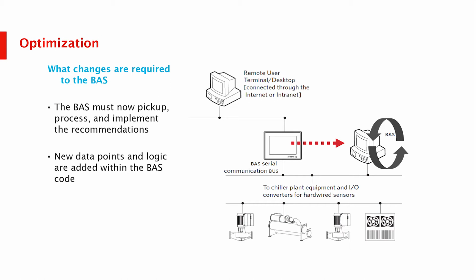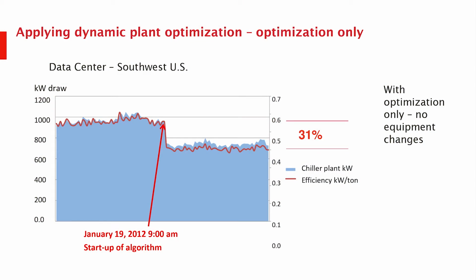And what's required? There's not a lot of changes required of the BAS. There's fewer than 20 points that need to be harmonized. For those that really want to take notes: number of chillers running, number of towers running, number of fans, fan speed, condenser pump speeds, chilled water pumps, chilled water speed, and chiller supply set point, and that's it. So those are the points that we would need to get, and then we send this speed recommendation. So this is not unique to our organization.